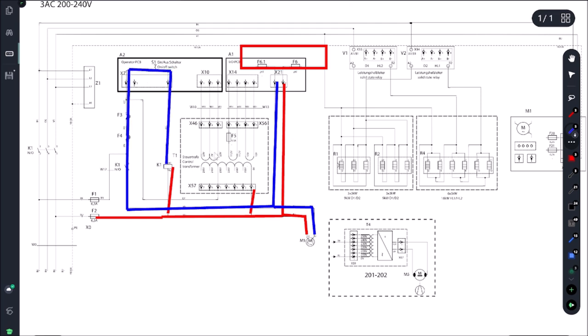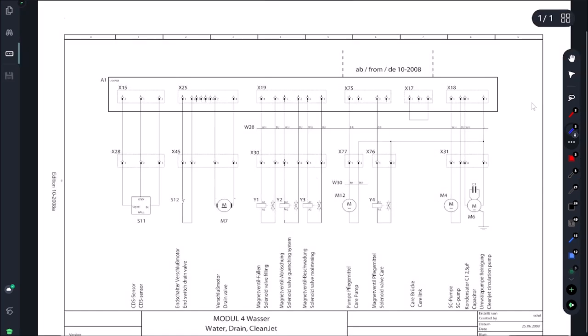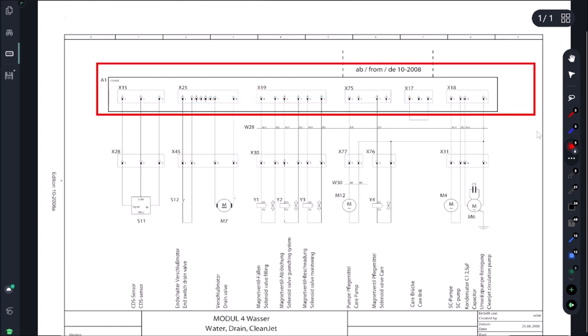What gets even more confusing is these fuses also run everything on this A1. So that means our dead short could be on our emptying pump M6, clean jet pump, solenoid valve.